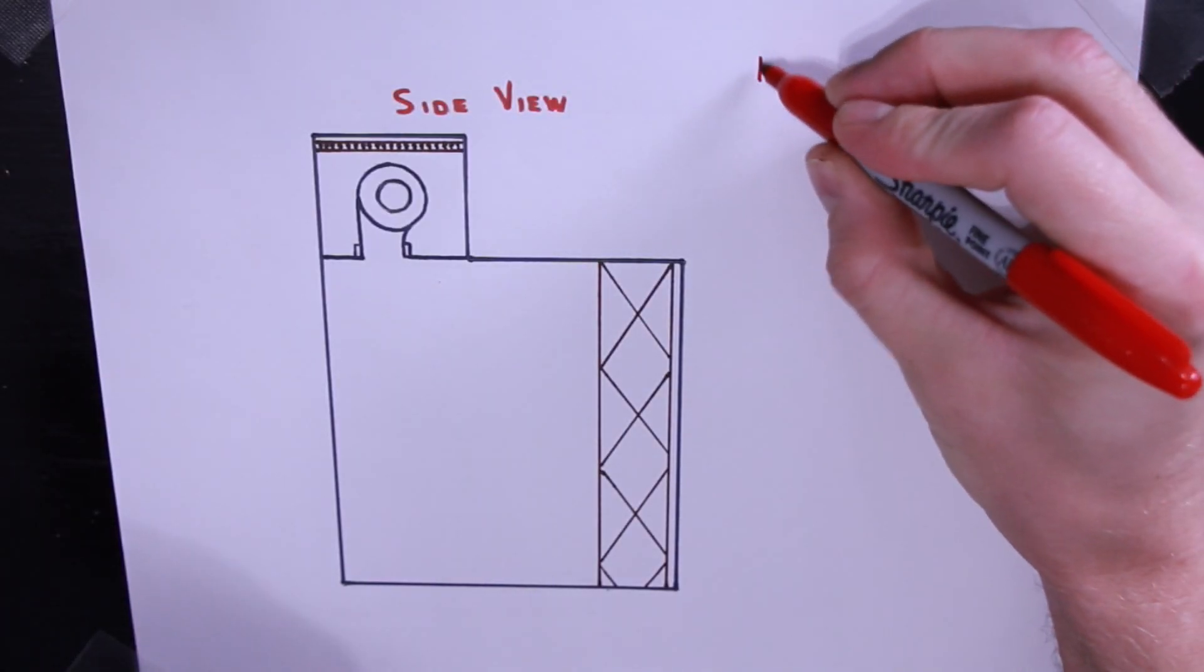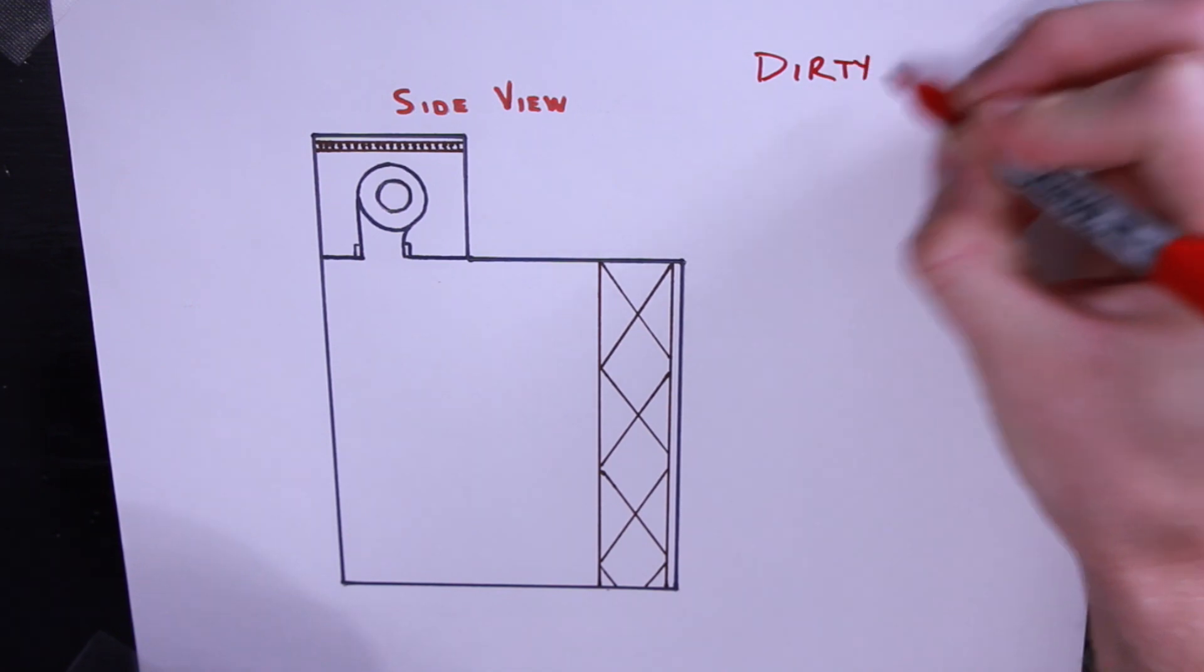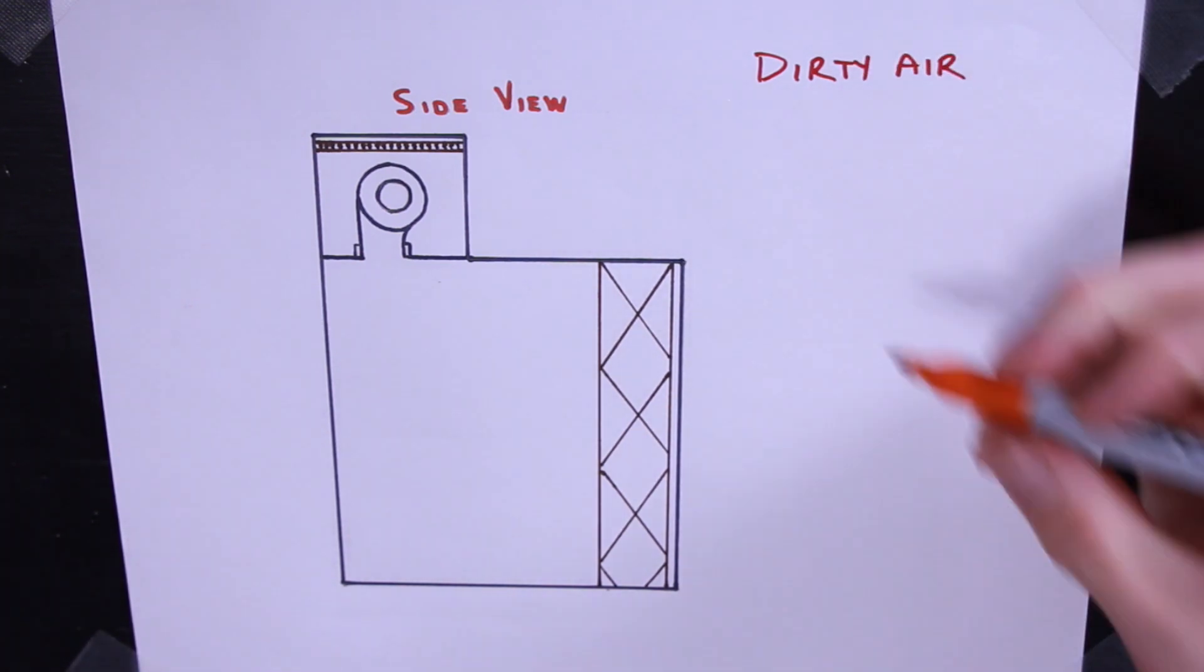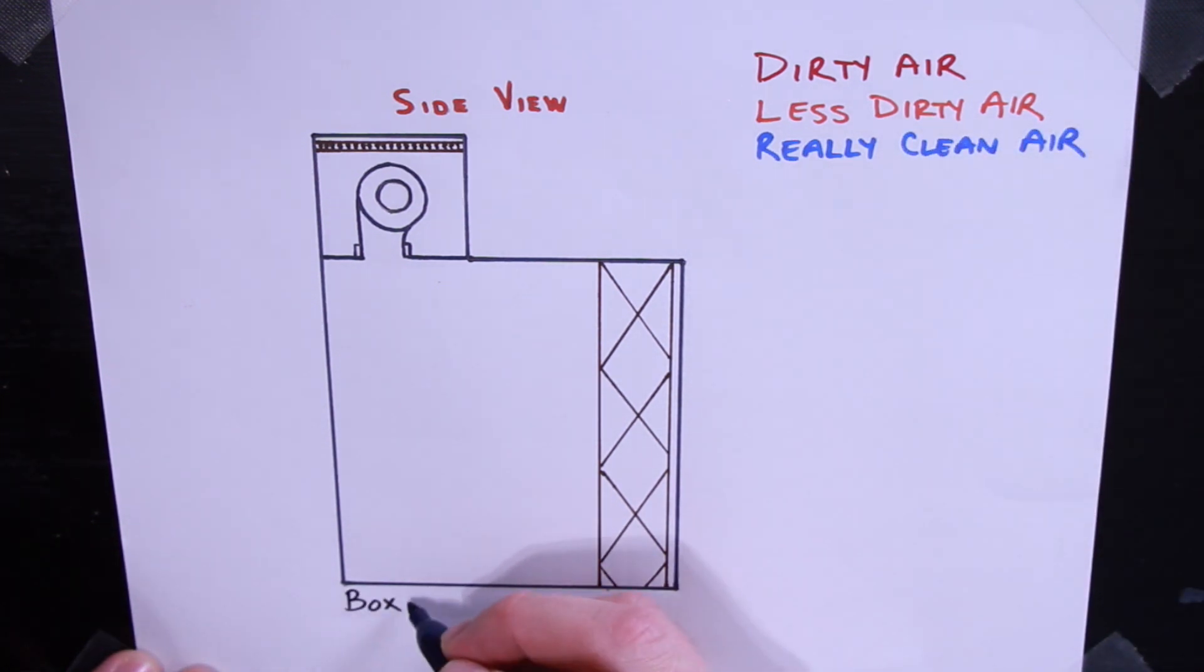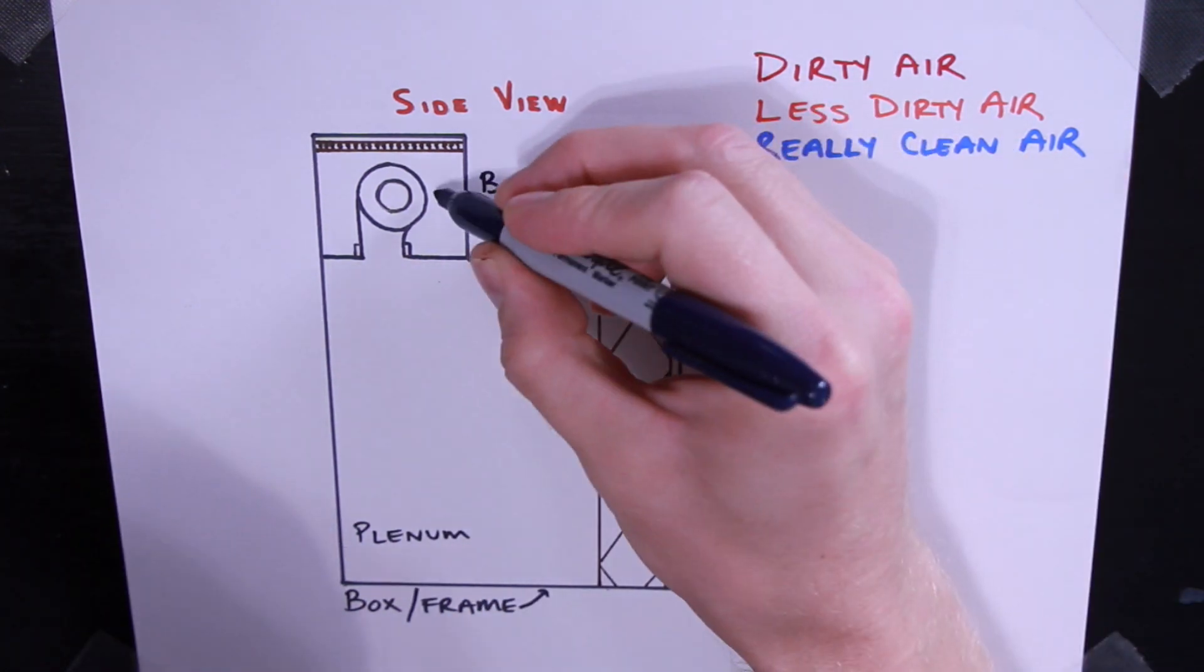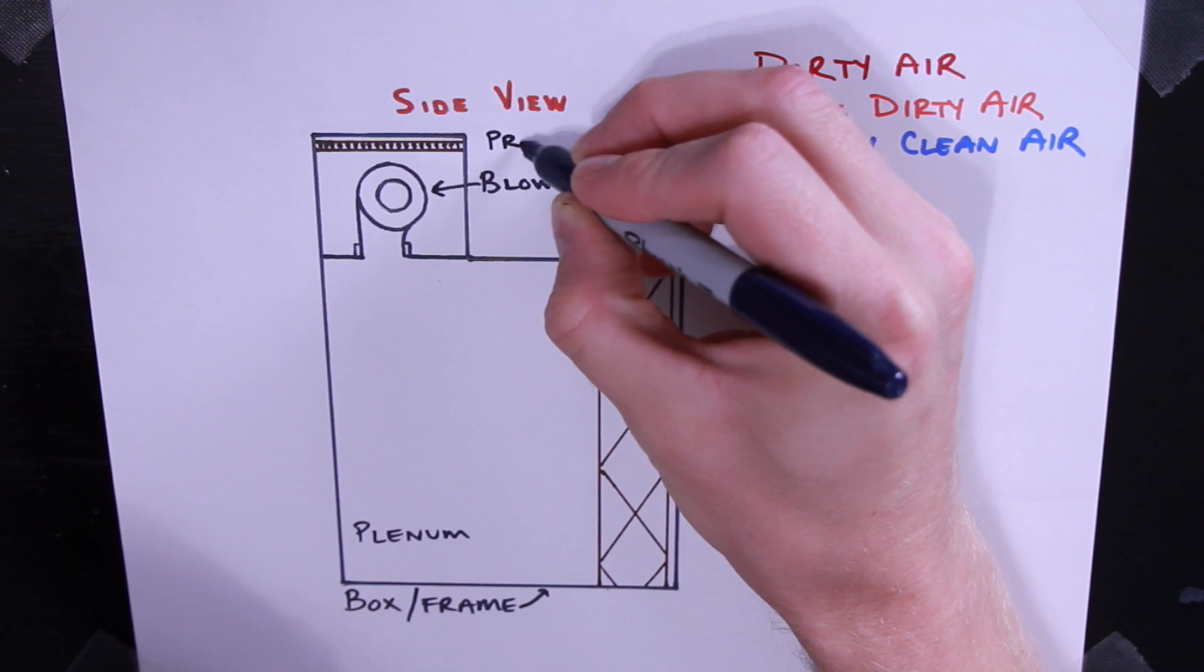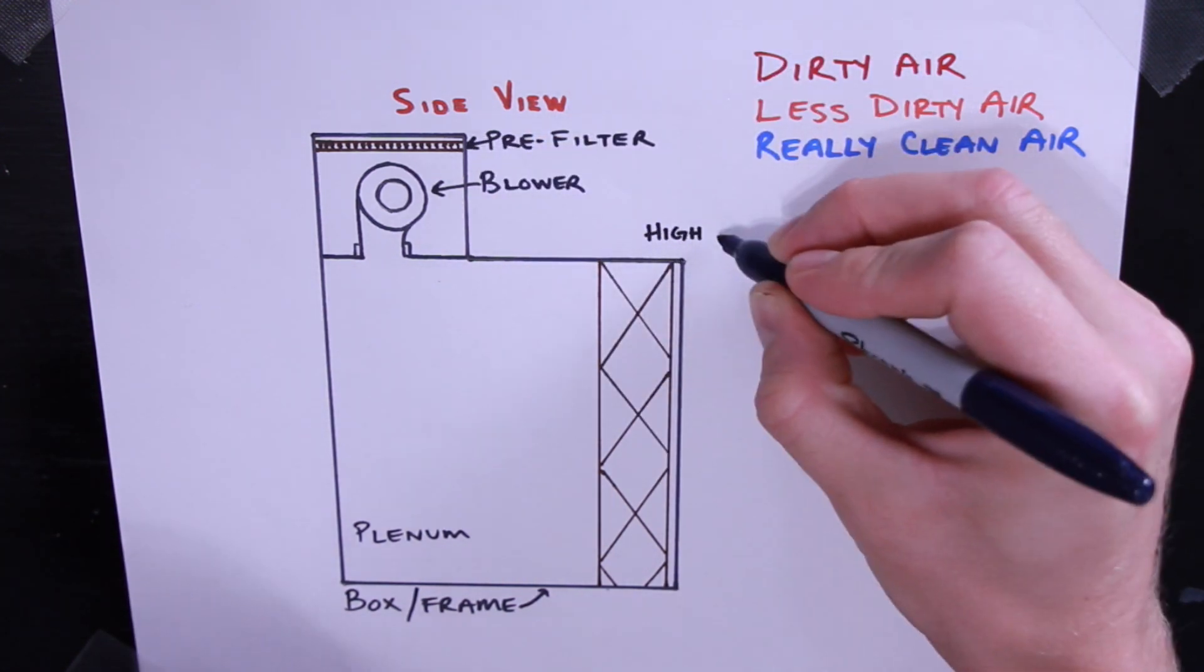In this illustration, we're going to use red to indicate dirty air, orange to indicate air that's a little bit less dirty, and blue to indicate really clean air. This is the layout of a typical laminar flow hood. We have a box or a frame, a plenum, a blower motor, a pre-filter to screen out any big dust particles, and a high-efficiency particulate air filter, also known as a HEPA filter.